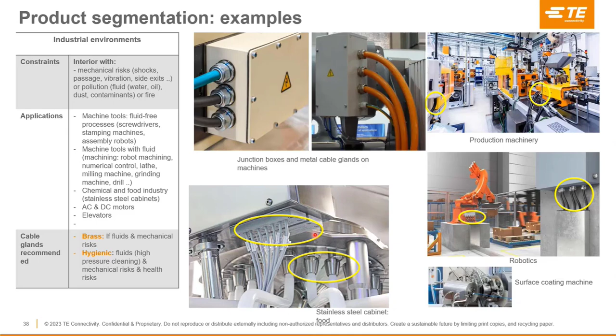Now, if you are outside but have low mechanical risk, that's something you find in HVAC, where you have a panel on the roof, so not so many people are going there. Solar inverters, combiner boxes, all these are installed in protected areas, so there's no real risk. So here again, you'll find plastic elements appearing.